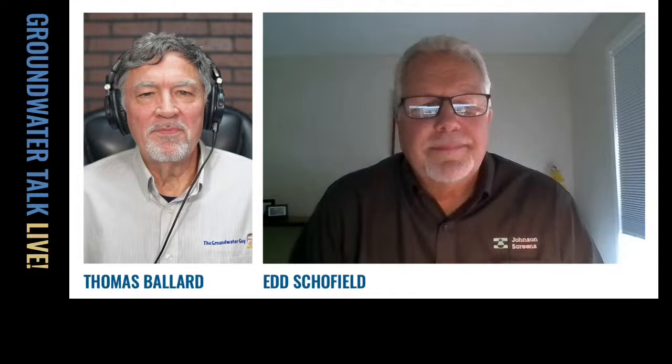That's for sure. Yeah. And not going to be my responsibility, but I had a site in California. It was a little nonprofit camp for blind kids. Their MO was they'd drill a new well every 10 years because the well would run out of water and quit pumping, so they'd just go out and drill a new well. That seems like a pretty short time span. We went in and looked at it, and they were basically getting some really heavy iron bacteria plugging going on. So instead of drilling a new well, you just go in and clean it out and treat it accordingly. They were going for their fifth well, and it was just crazy.